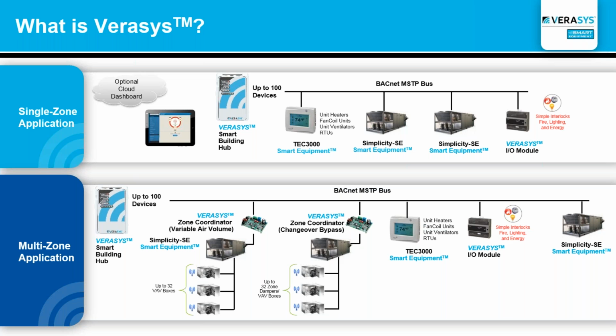To make it a little more interesting, now we're talking about zoning. So basically the same architecture with one smart building hub that could go up to 100 devices - yes, 100 rooftops. Out of those 100 rooftops, 10 of those can be zoning. And for each zoning, it could be a mixture of changeover bypass or VAV. For each system of the zoning, we could handle about 32 VAV boxes or 32 changeover bypass zone dampers.